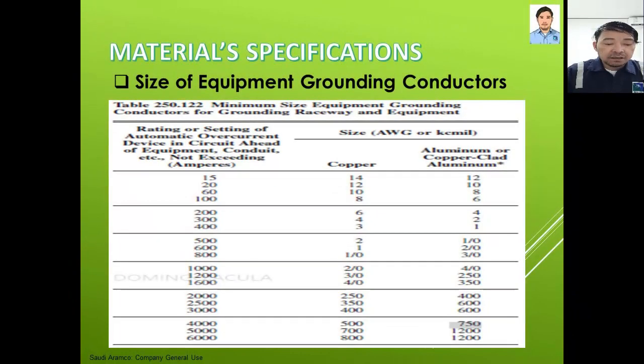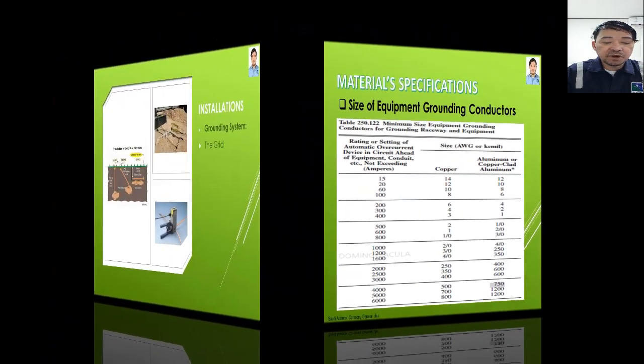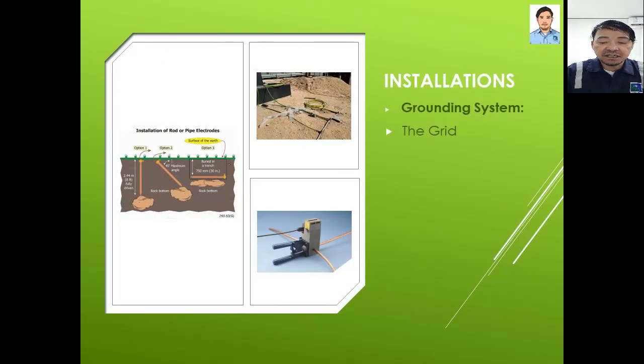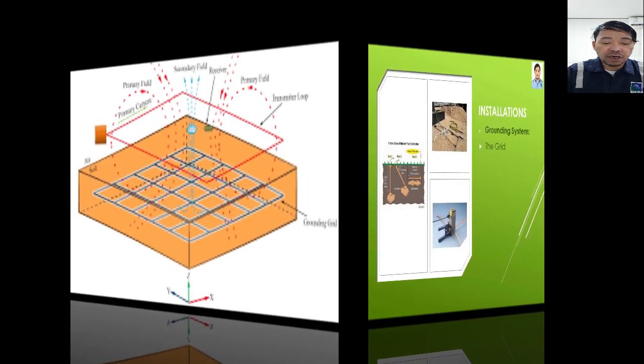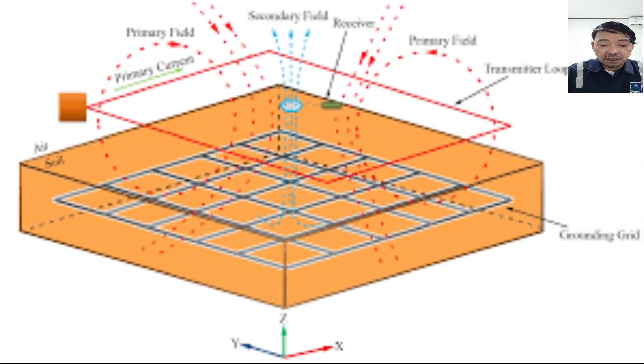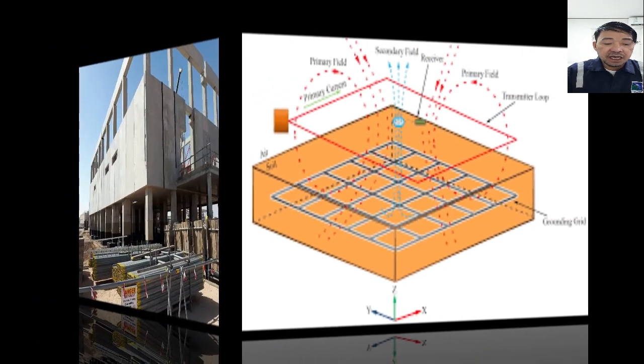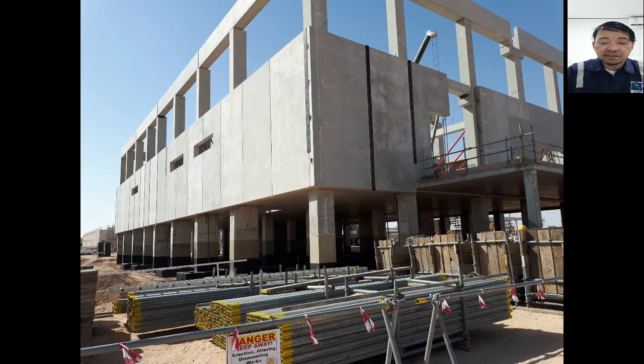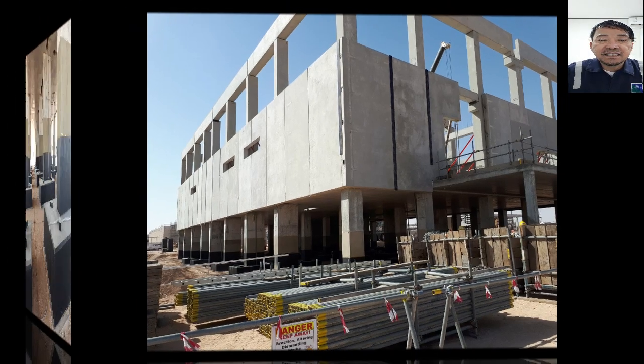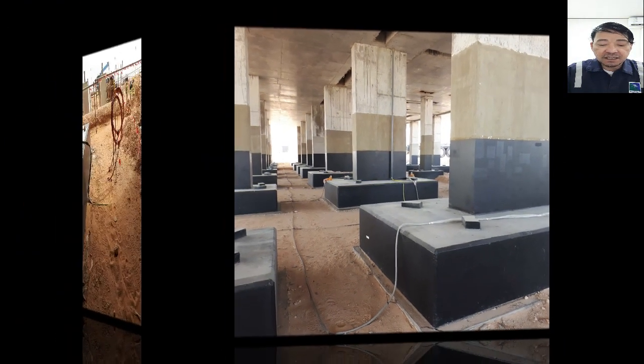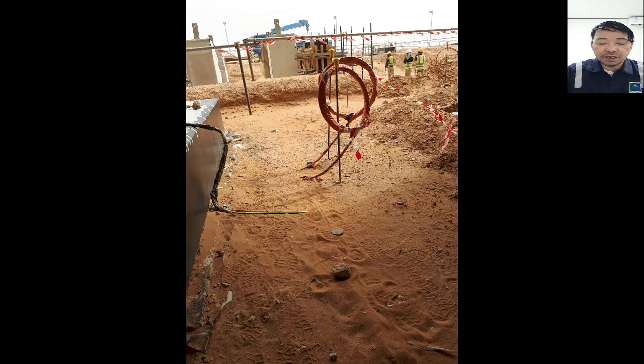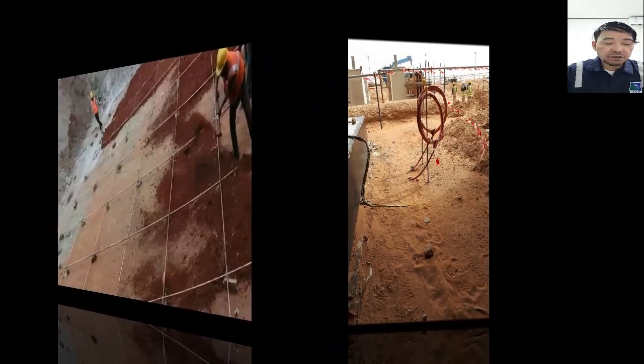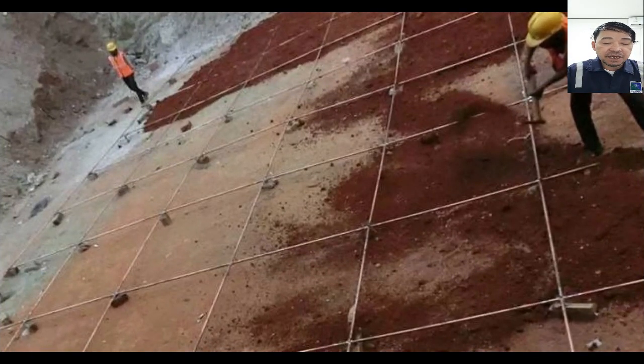Grounding grid. Ground grids are installed at a depth such that the fault currents flowing in from the above grade steel structure are easily dissipated into the earth. As per SAES-P-111, paragraph 7.1.3, a combination of rod or pipe electrodes in a grid or loop of bare copper conductors is buried a minimum of 460 millimeters. Substation ground grid shall be constructed of minimum 70 millimeters squared or 2/0 AWG stranded bare copper conductor.